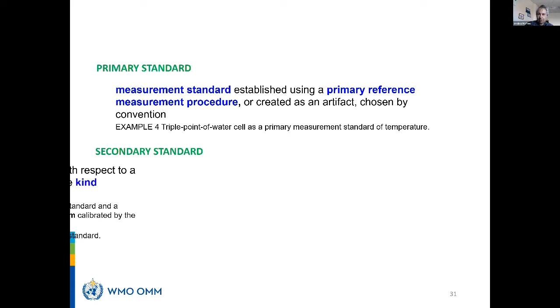And then you have the secondary. The secondary is linked to the primary through a calibration. And the calibration can be obtained by comparison, for example, or through some standardized procedure of assigning a value from the primary to the secondary standard. So there are procedures for each quantity. Secondary standards can also be for derived quantities. Normally national standards are also for derived quantities. For example, we have the national standard for pressure, which is a derived quantity, not a primary quantity, and so on.